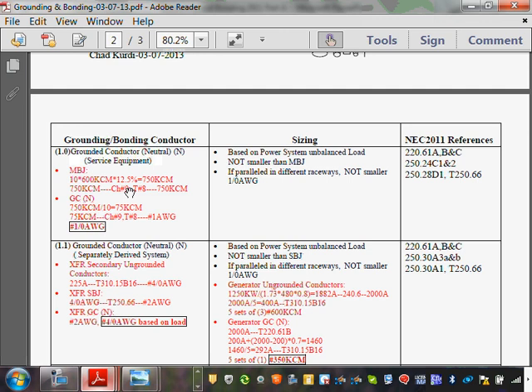By the time you reach the 4,000 amp switchgear, guys, everything is balanced. That's carrying the unbalanced load. Not a whole lot. When you reach up to a 4,000 amp switchgear, everything is balanced. So you have 10 conductors, 1/0 AWG each, 1 in every conduit. That's your neutral that's bringing the power to the building, minimum. If you decide to go put 4/0 AWG, bring it on, right? For 250, bring it on. So that's your minimum. Any comments, guys, about these?